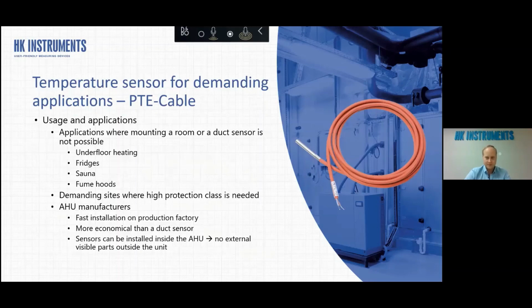And then we have this cable sensor, and the material is silicon, so it can withstand a really wide scale of different temperatures. So normally they are with PVC, but this one is silicon, so you can use it also with the more demanding applications, such as underfloor heating or some fridge. And because we are from Finland, we wanted to make sure that this is also feasible in the sauna and also in the fume hoods. And typically these cable sensors are a good choice for the air handling unit producers, because they can easily put this inside the unit instead of this duct sensor.